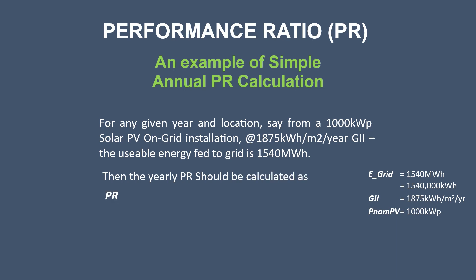Then the yearly PR is calculated as 1,540,000 divided by (1875 multiplied by 1000), which gives 0.82, or 82%. So hopefully you now understand how to calculate the annual performance ratio of a solar plant.